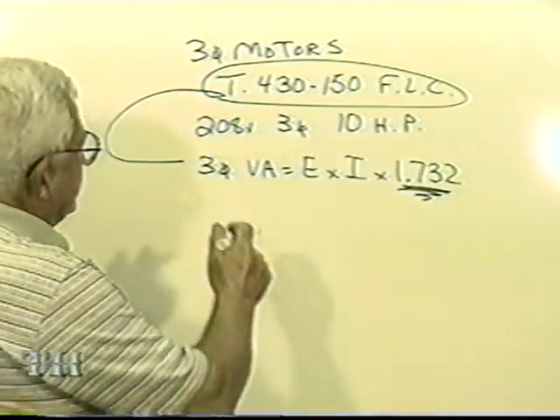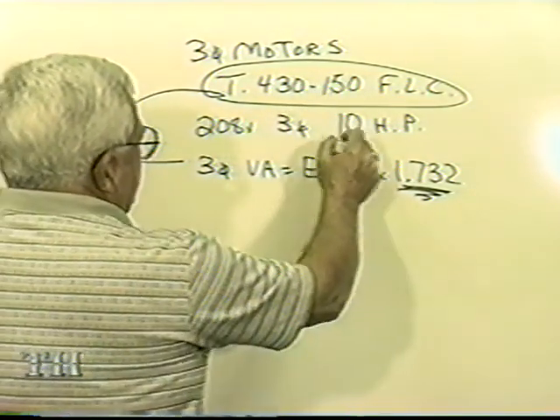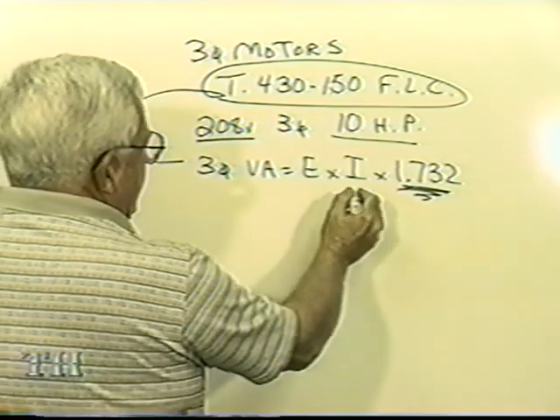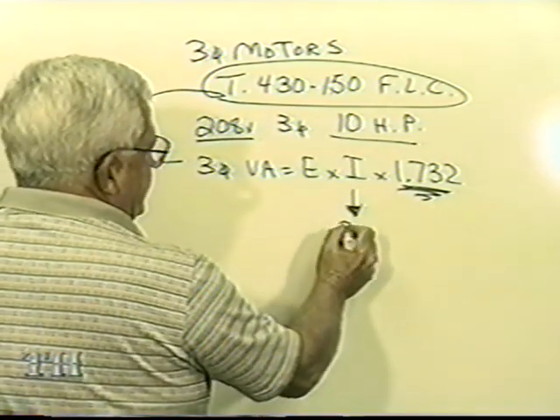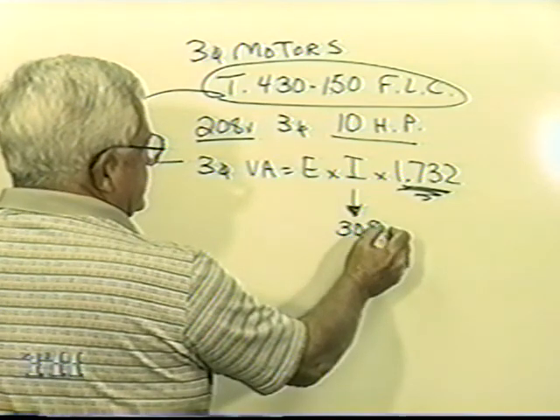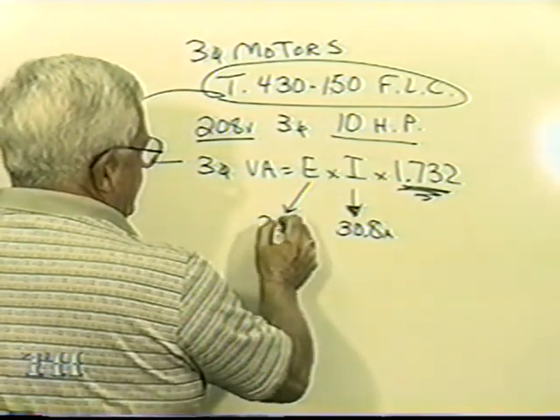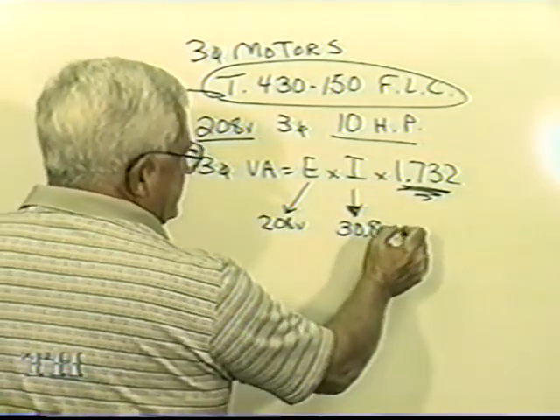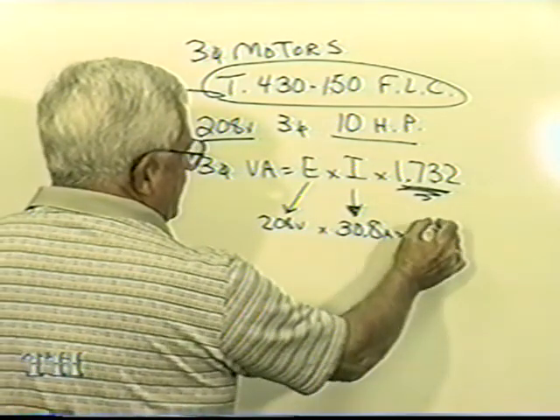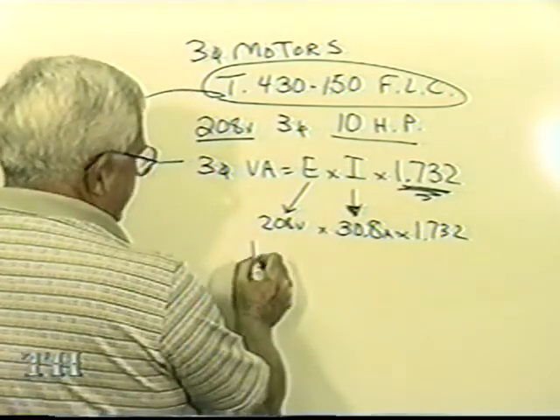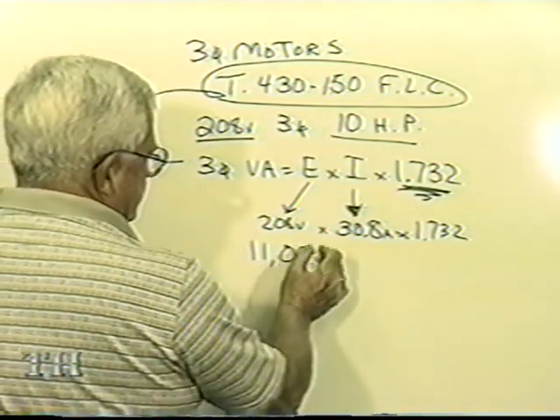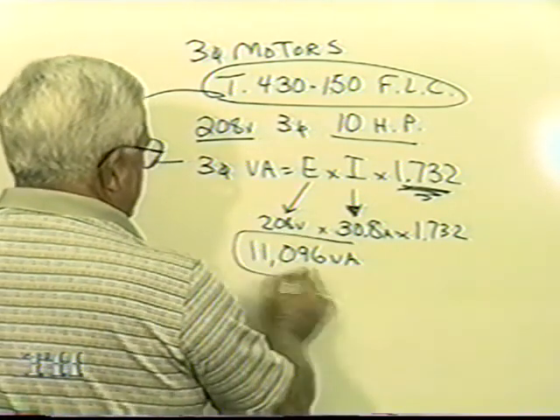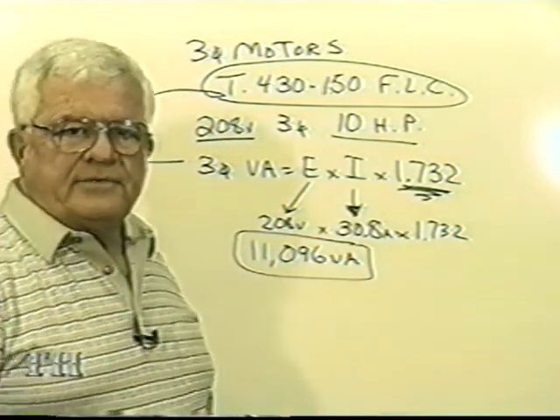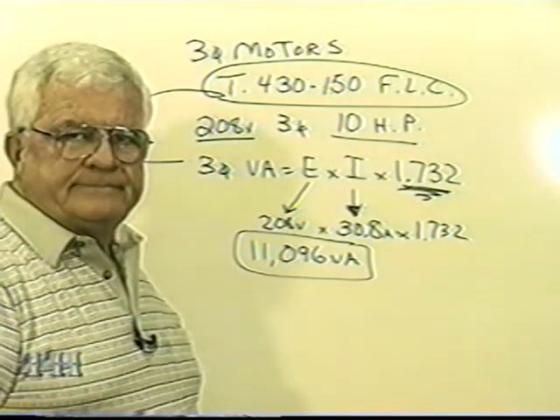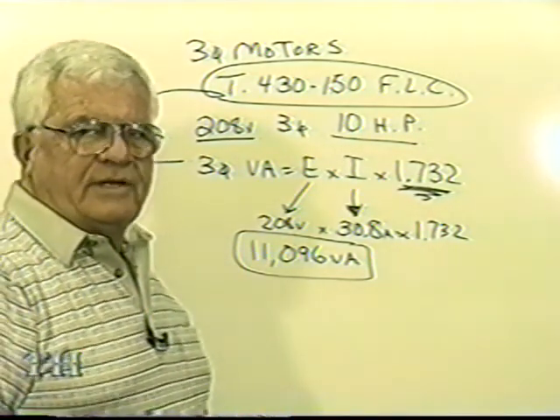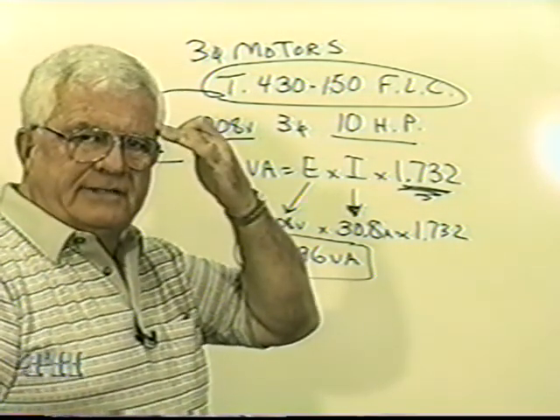But see, I've done this long enough. I know if I go to this table for 10 horsepower, 208, this guy is going to be 30.8 amps. And this guy is 208 volts. And if I take these at the square root of 3, this is a question they've asked for 30 years. Here's the answer: 11,000, rounded up, 96 volt amps. 11,096. I got it filed right here.